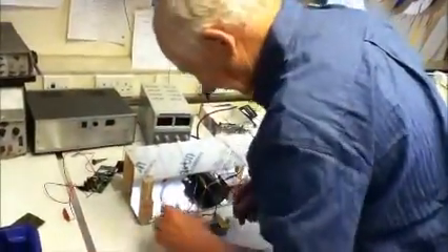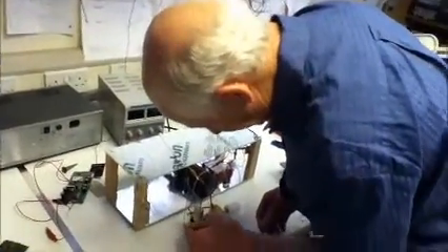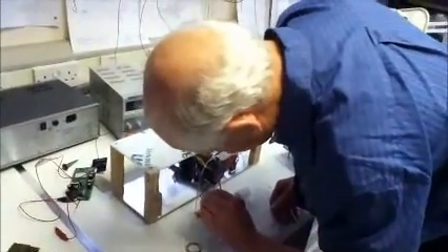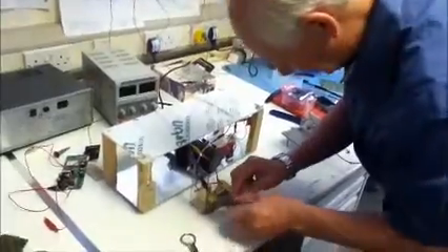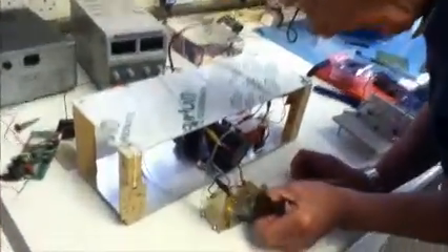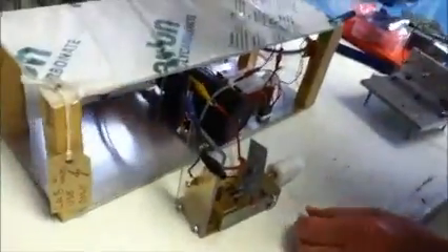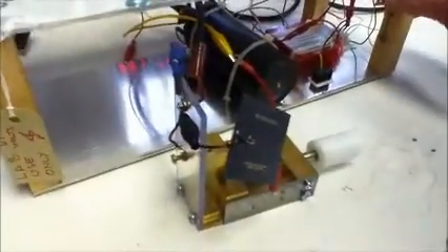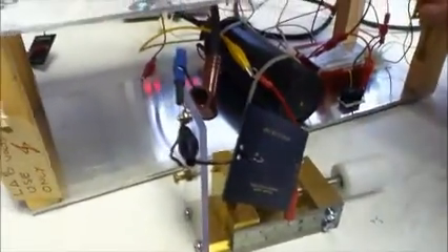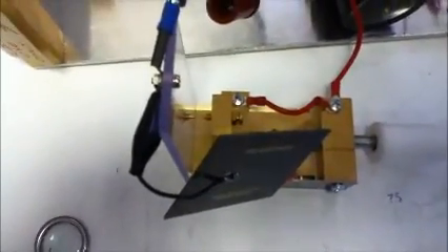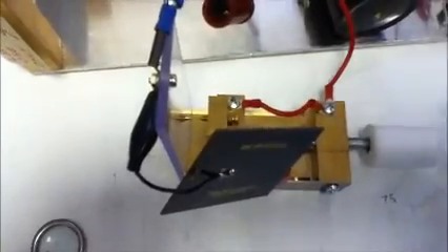If I put this one on, which was designed with true attention to creepage and clearance, I'll just ground it to here, turn the power supply back on, and in fact, if you can get in there, you can now see that at that voltage it's now choosing to jump the spark gap. And with this one we can take it out to 3 millimetres, which is 10 kilovolts.